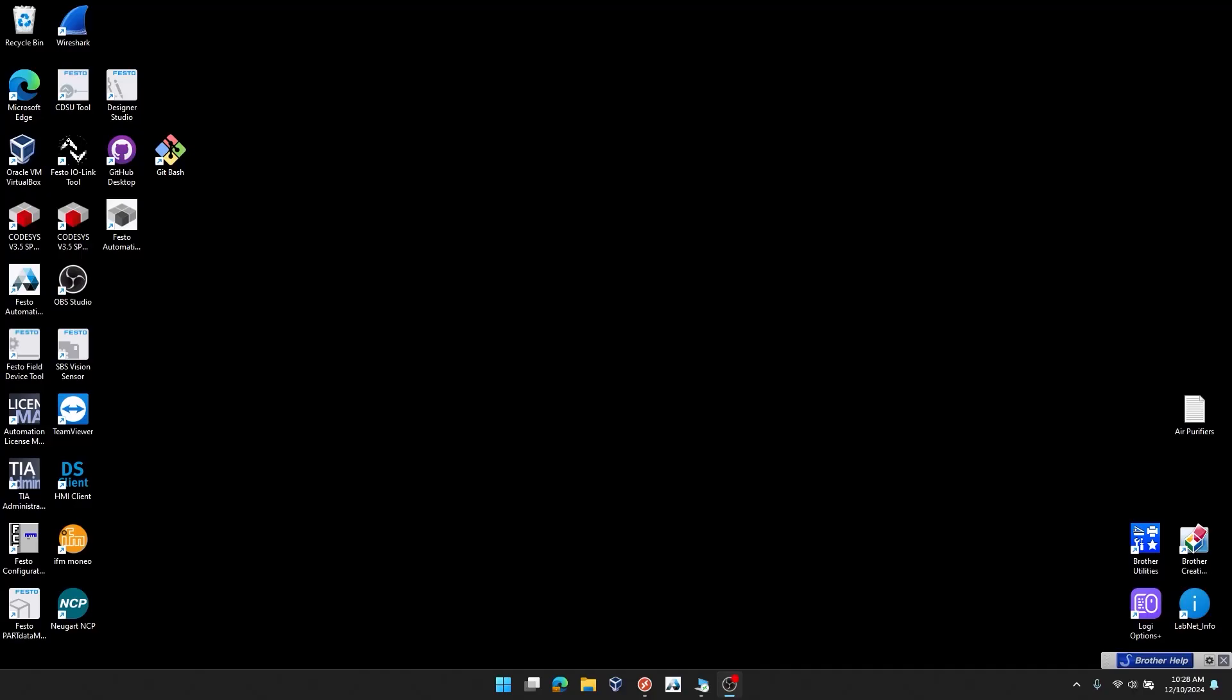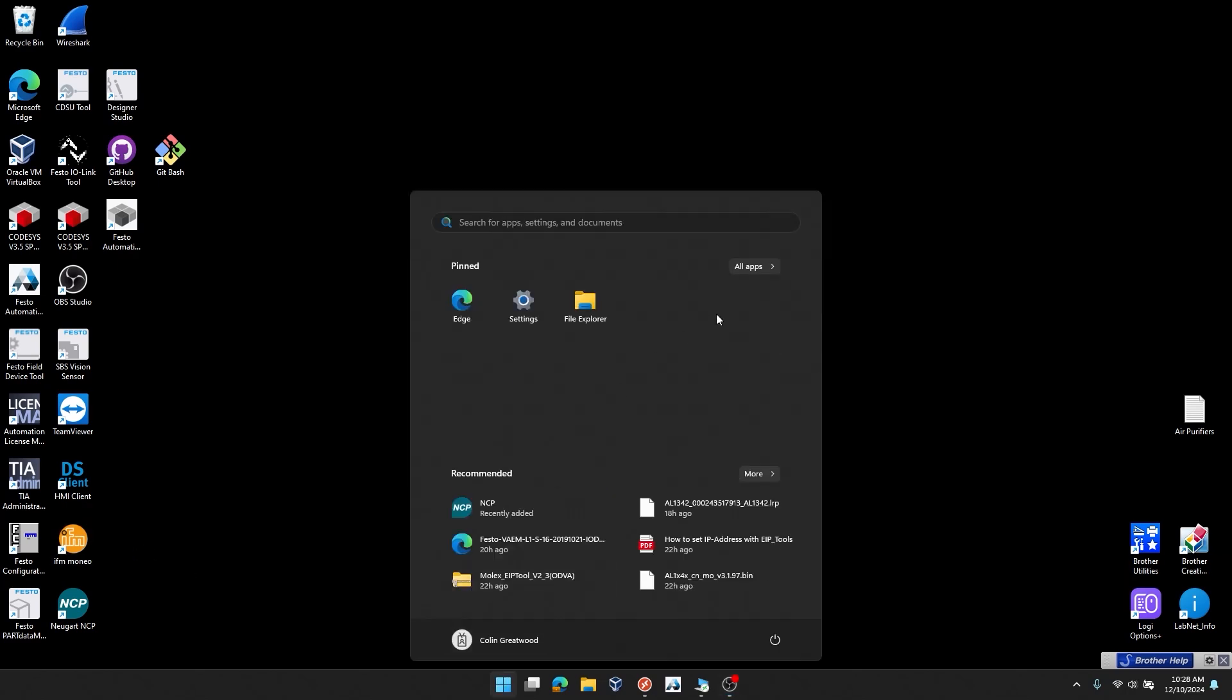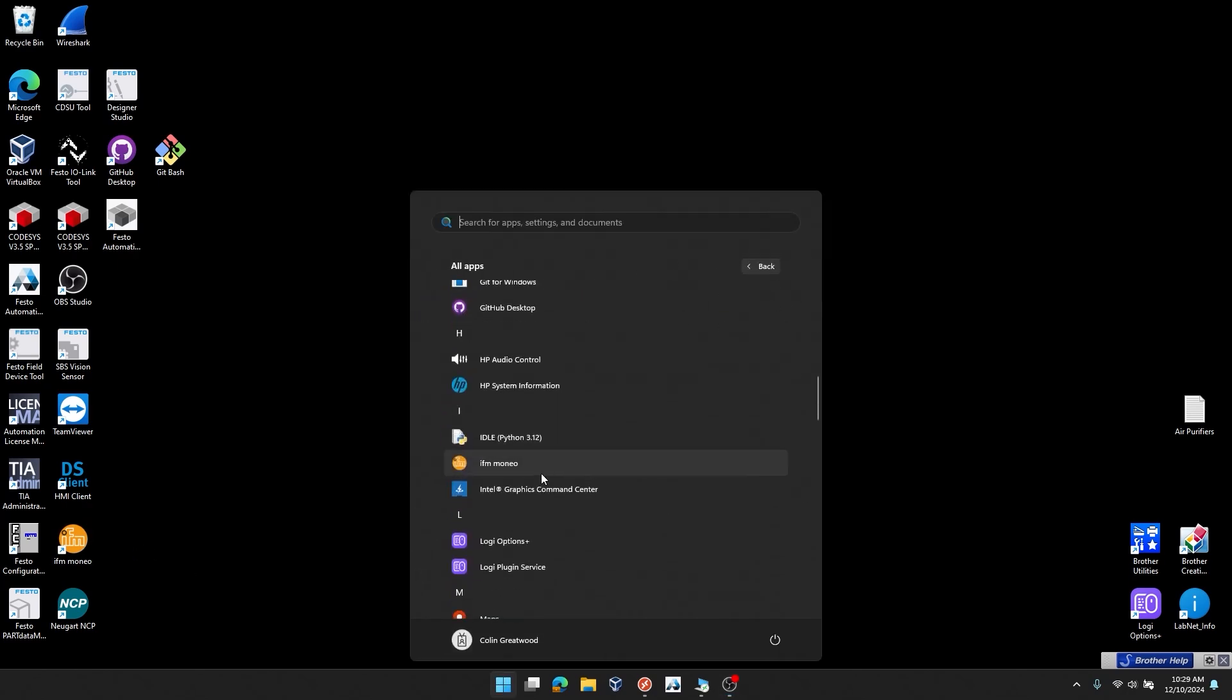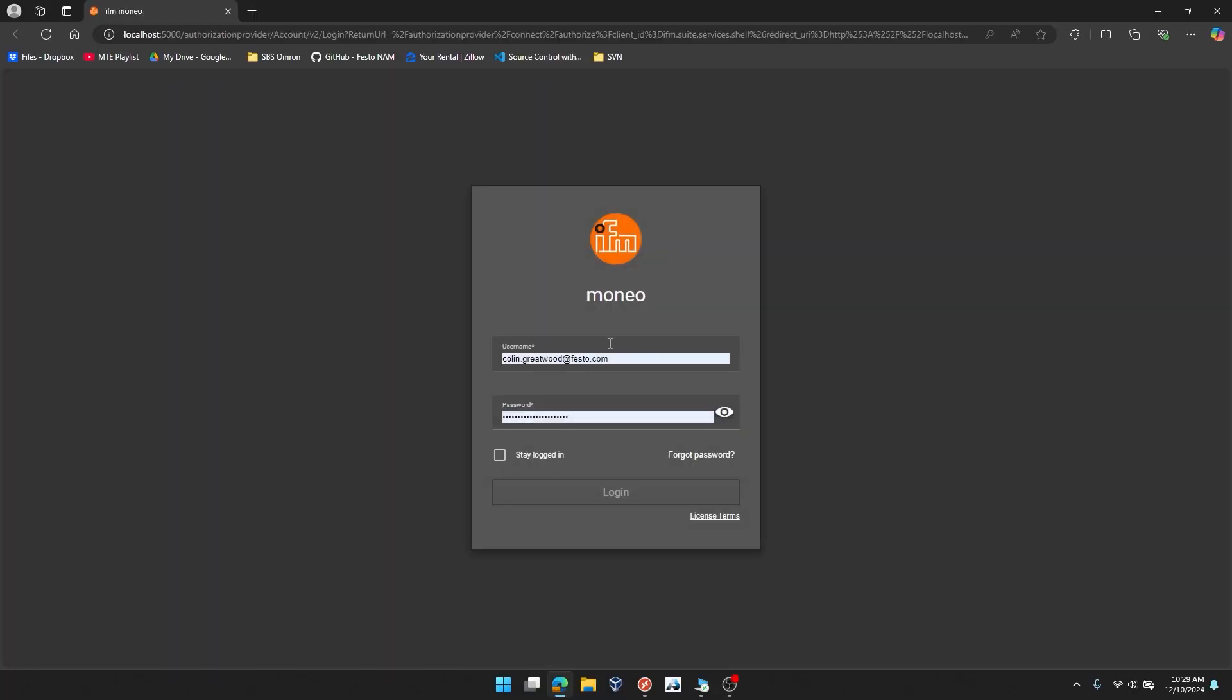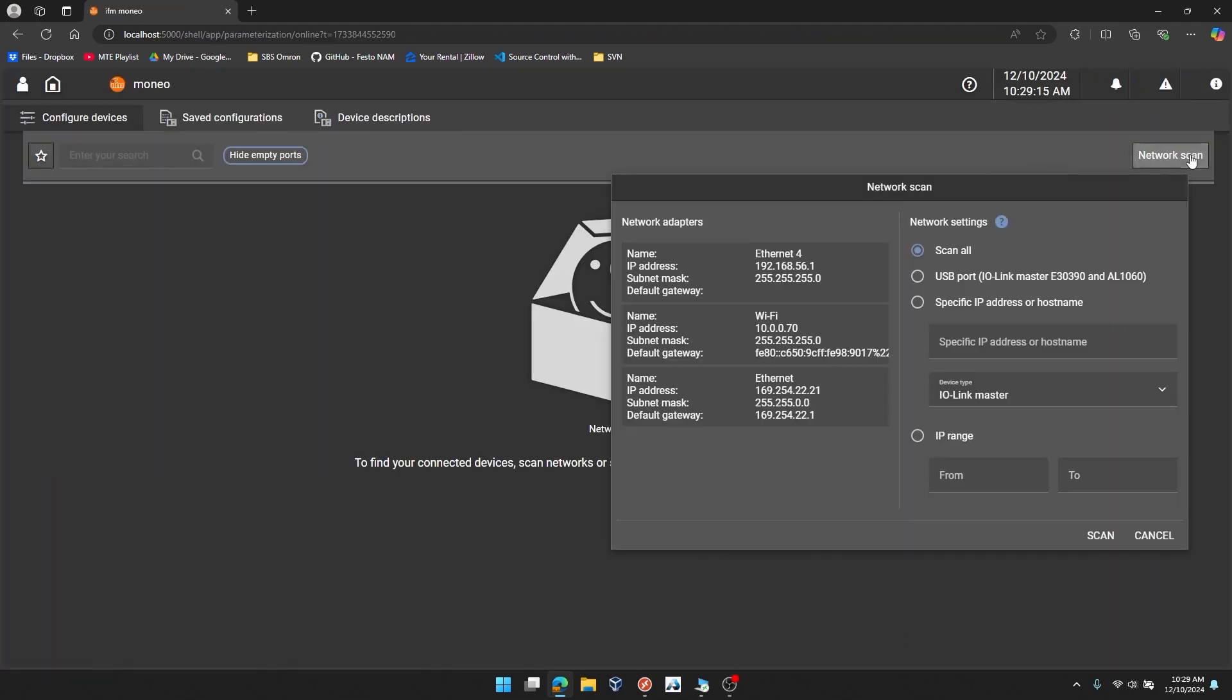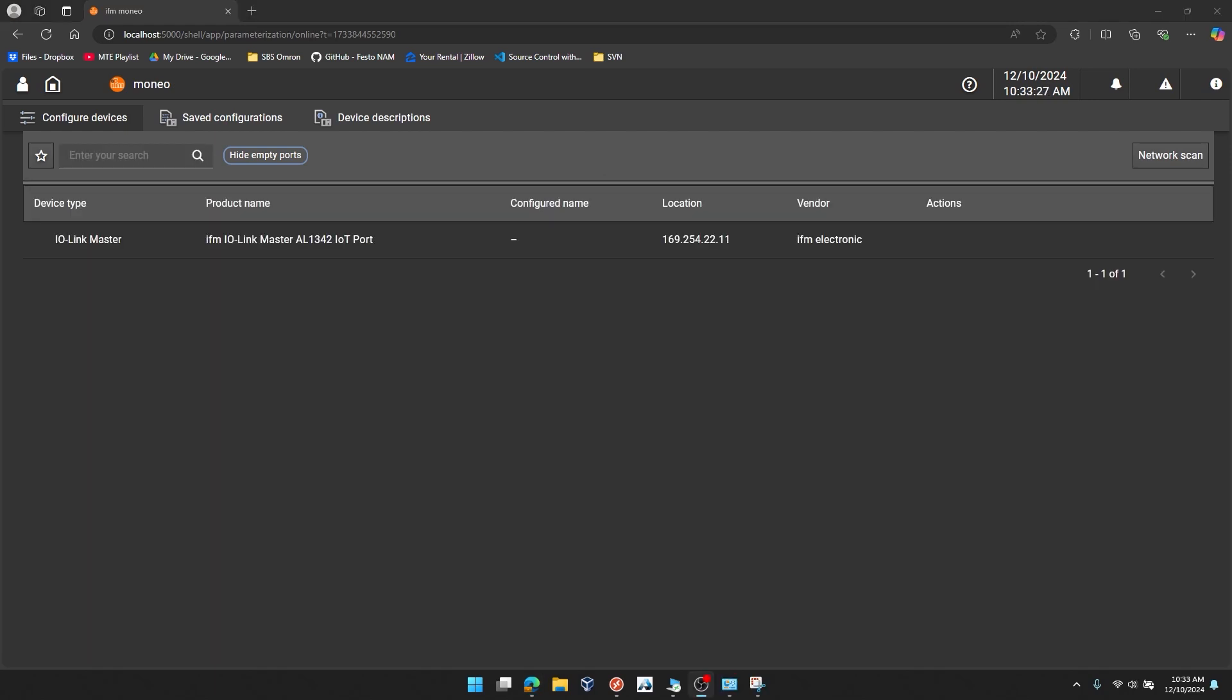Now transitioning over to my laptop, I will start with factory resetting the IO-Link master, just so I can show that this is going to be the same thing as if you had pulled the IO-Link master off of your maintenance shelves or stores. So I'll start by going to IFM Moneo. I can go into my apps and launch IFM Moneo. Obviously, you'll need to create a login here if you have not done so, which I have. I'll log in. And I can perform a network scan, scan on all ports. Once my device scan has completed, you can see that I am now seeing the IP address of the IoT port for my AL1342.